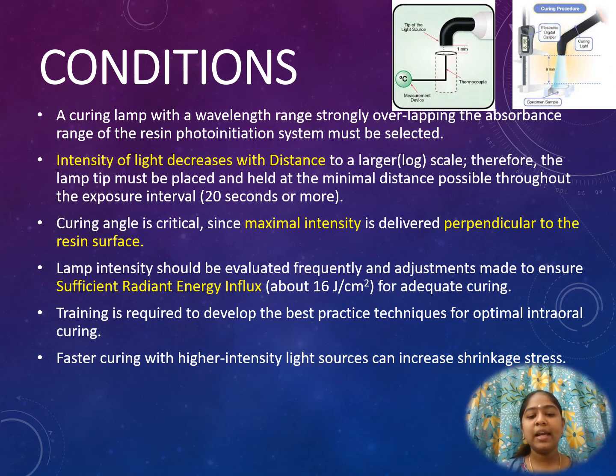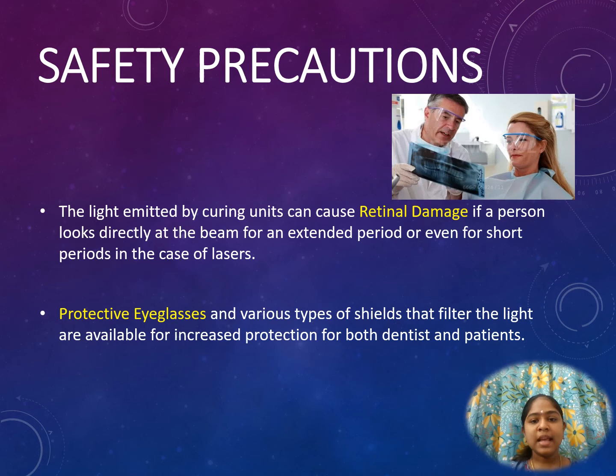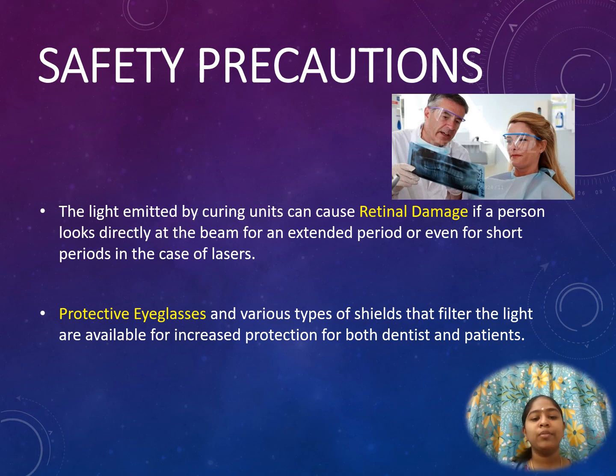Faster curing with higher intensity light sources can increase shrinkage stress. Safety precautions to be followed while using curing lamps: the light emitted by curing units may cause retinal damage if a person looks directly at the beam for an extended period, or even for a shorter period in the case of lasers. To avoid such damage, never look into the light tip and minimize observation of the reflected light for longer periods. Protective glasses and other types of shields may be provided to increase protection for both the dentist and the patient.